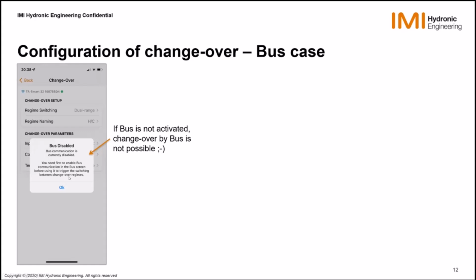Makes sense. We force the people to go to the bus screen because it's not just about choosing Modbus RTU or BACnet. As you know, you need to specify an address and a few parameters to make the bus communication work. So we invite people to go to the bus screen themselves, set up their bus properly, and then come back to changeover to assign a changeover by bus.